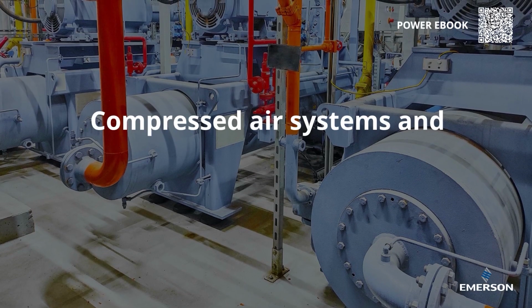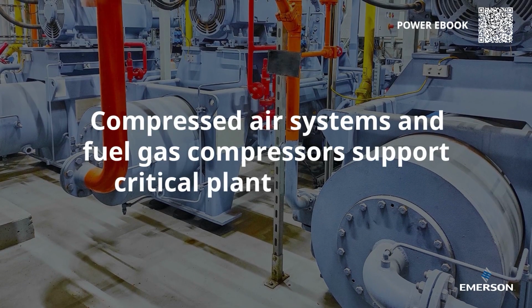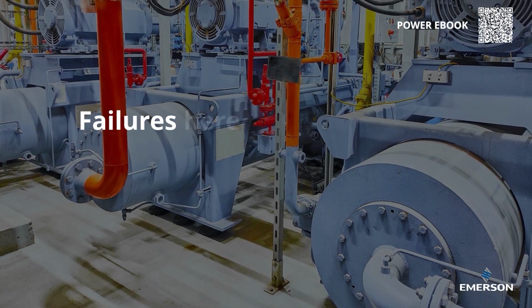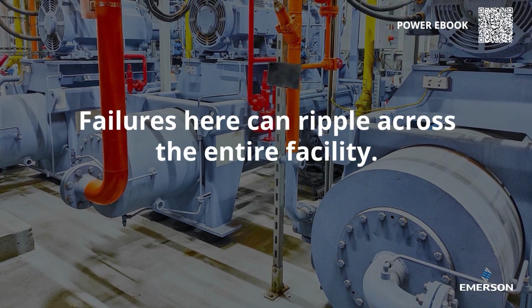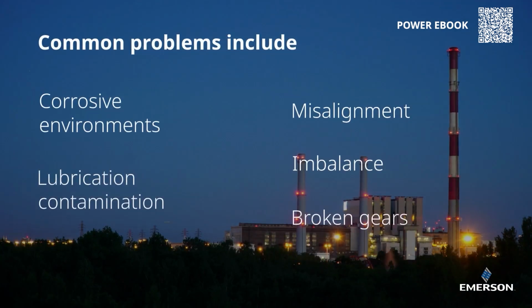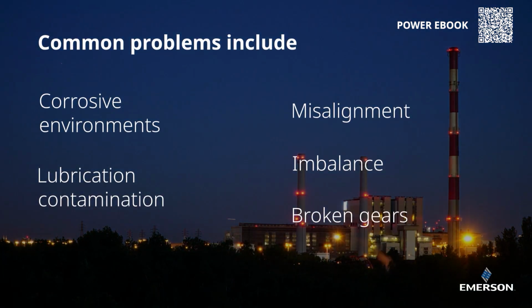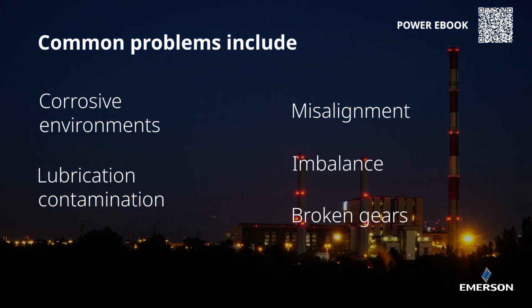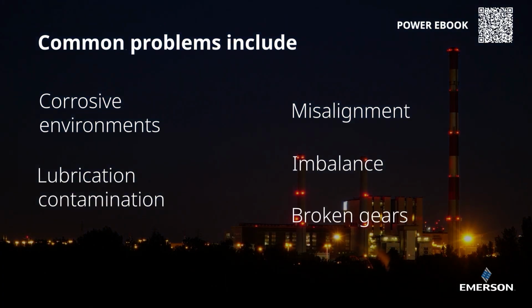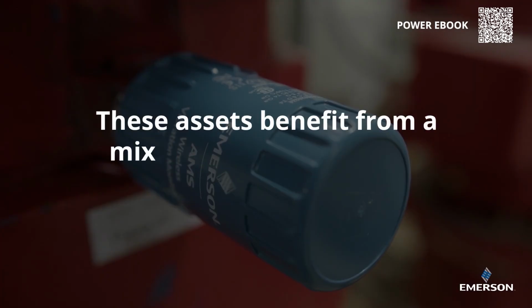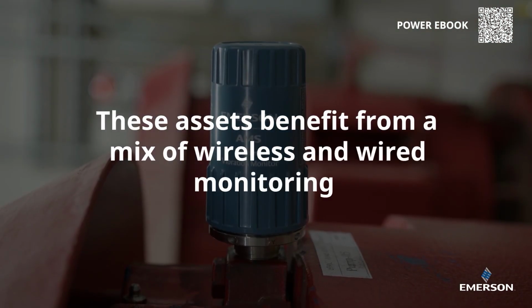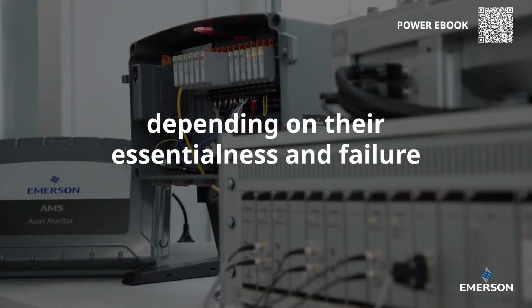Compressed air systems and fuel gas compressors support critical plant operations. Failures here can ripple across the entire facility. Common problems include corrosive environments, lubrication contamination, misalignment, imbalance, and broken gears. These assets benefit from a mix of wireless and wired monitoring, depending on their essentialness and failure modes.